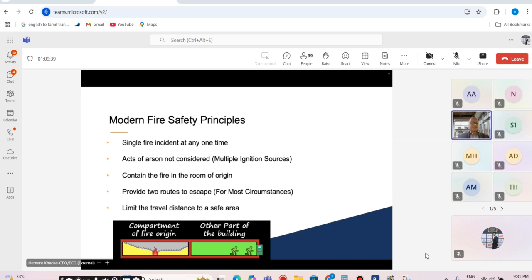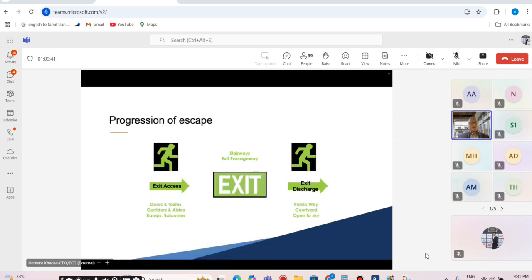And then travel distance becomes the important criterion. So when you look at the egress, there are three components from the place where you are on any floor. The first is that you are trying to reach the nearby exit, and that's the reason it's called exit access. That's the first means of escape or means of egress. When you identify the fire exit, which is a staircase that is protected, separated, segregated, you use that as an exit and go to the exit discharge as the last means of escape. And that's how you complete the process of egress.